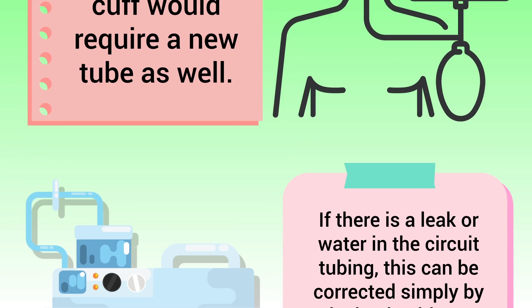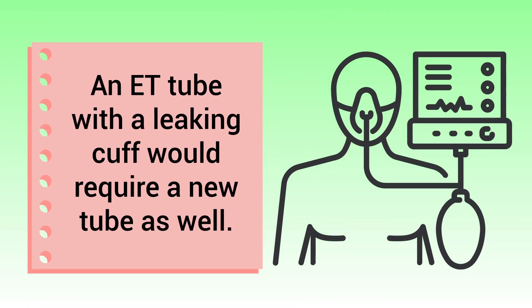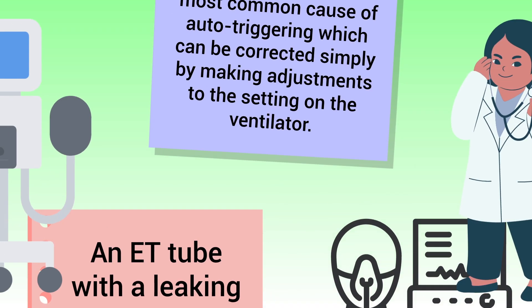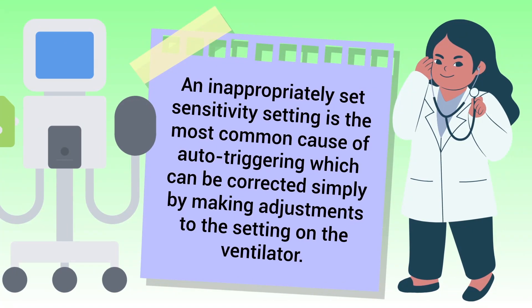An ET tube with a leaking cuff would require a new tube as well. But again, an inappropriately set sensitivity setting is the most common cause of auto-triggering, which can be corrected simply by making adjustments to the setting on the ventilator.